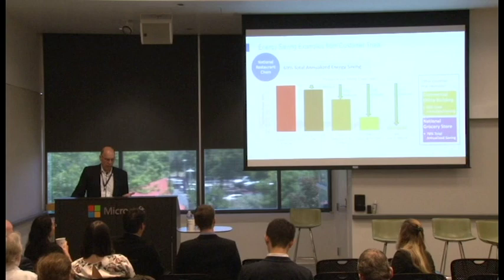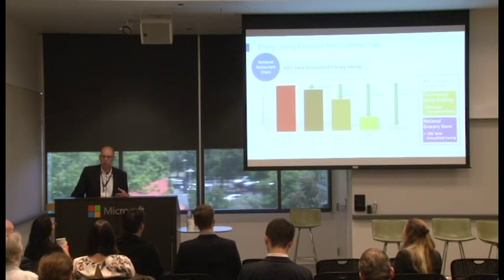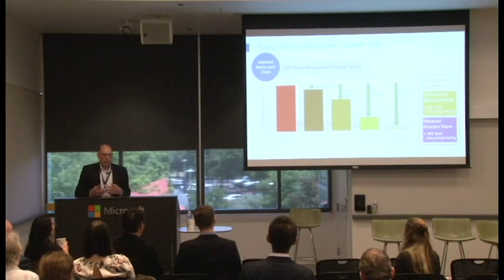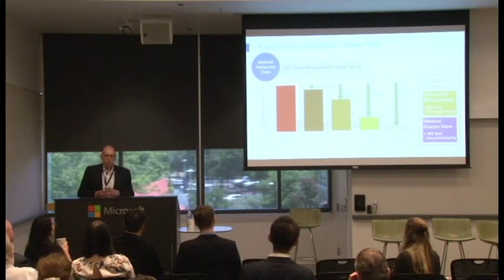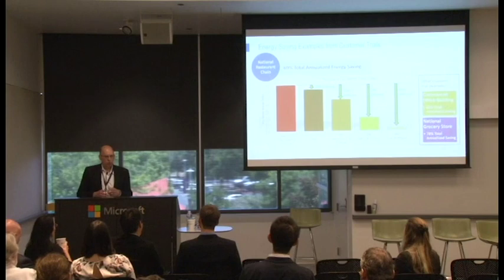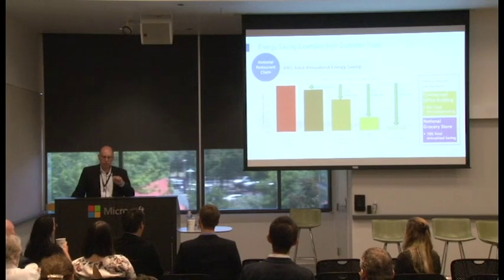We've also benchmarked against existing variable speed applications. So this was a fixed speed to a variable speed. We've benchmarked against variable speed applications. We're seeing 40 to 50% improvements even over an existing variable speed solution, which is intended to be the most optimal solution. And we get that energy efficiency gain because what most people don't realize is that traditional motors are only specified at their nominal operating speed. So in a HVAC application like this, your motor is specified to run at 1800 RPM and its efficiency is rated at 1800 RPM. When you deviate from that operating point, your efficiency drops dramatically. It can be as low as 50% in a lot of cases, whereas we maintain a flat efficiency curve across the entire operating speed range of the motor.